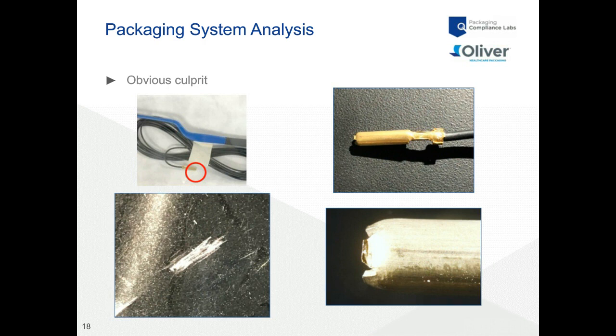When we took a closer look at the medical device, it all of a sudden became not so benign. We looked at the area where the abrasion was occurring—it was that little metal lead component you see there. In the lower right, you can see there's a really sharp edge on that metal component, and that was abrading through the film and causing problems.